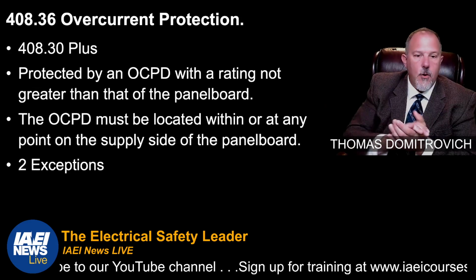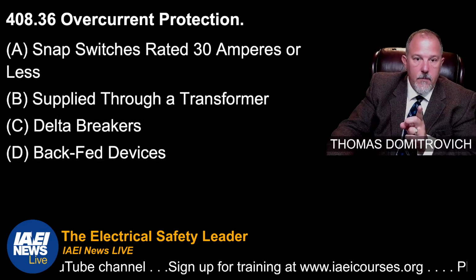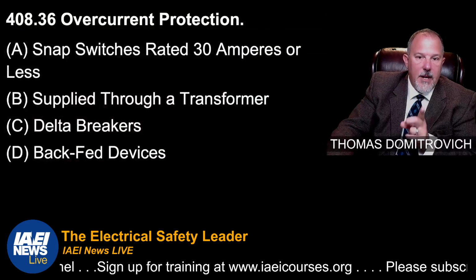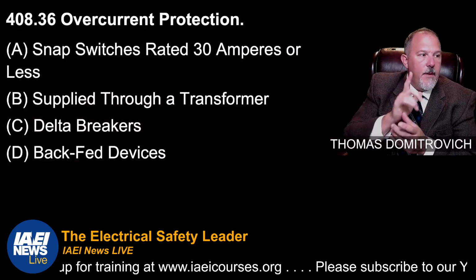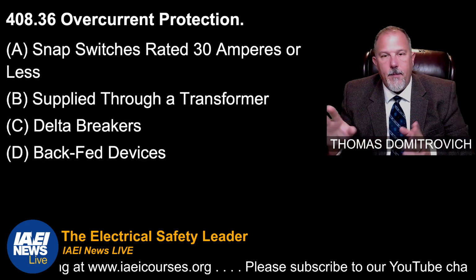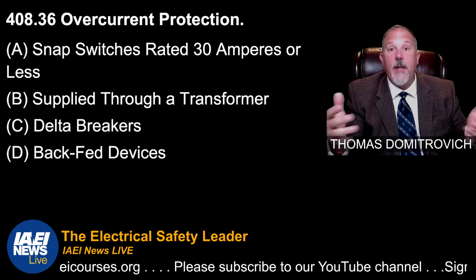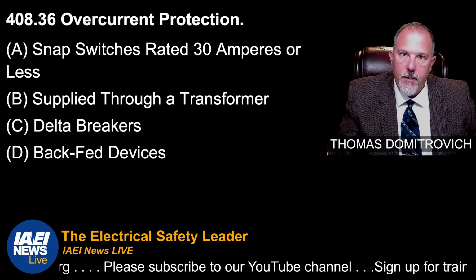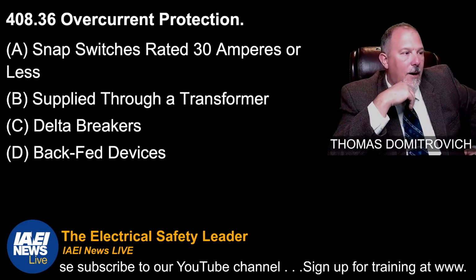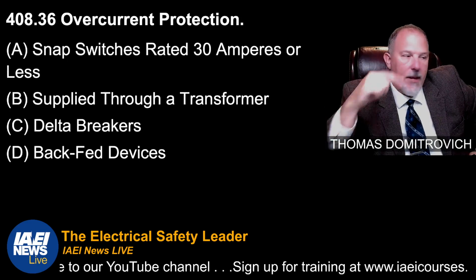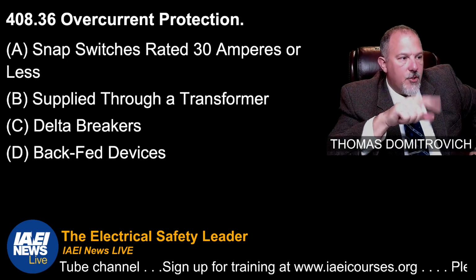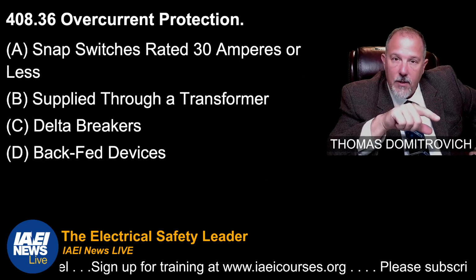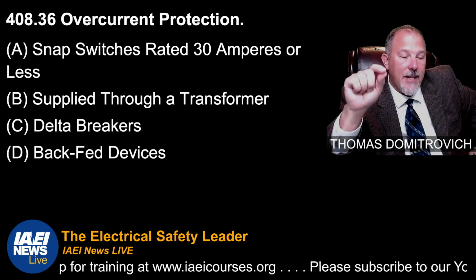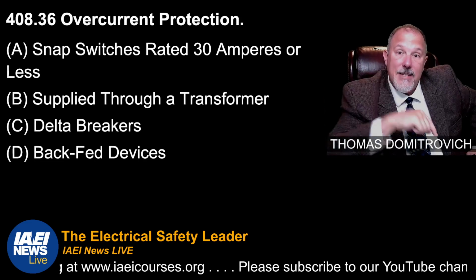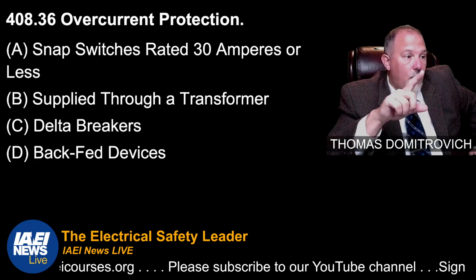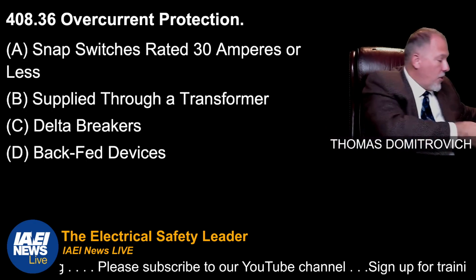In 408.36, supplied through a transformer. This is one that's very commonly seen: you have a panel board on the secondary of a transformer, and they'll say it's a main lug only panel board. And you go, main lug only. Well, how are you protecting that panel board? Where a panel board is supplied through a transformer, the overcurrent protection required by 408.36 shall be located on the secondary side of the transformer. Now, there is an exception, and the exception is when you are in 240.21(C)(1).